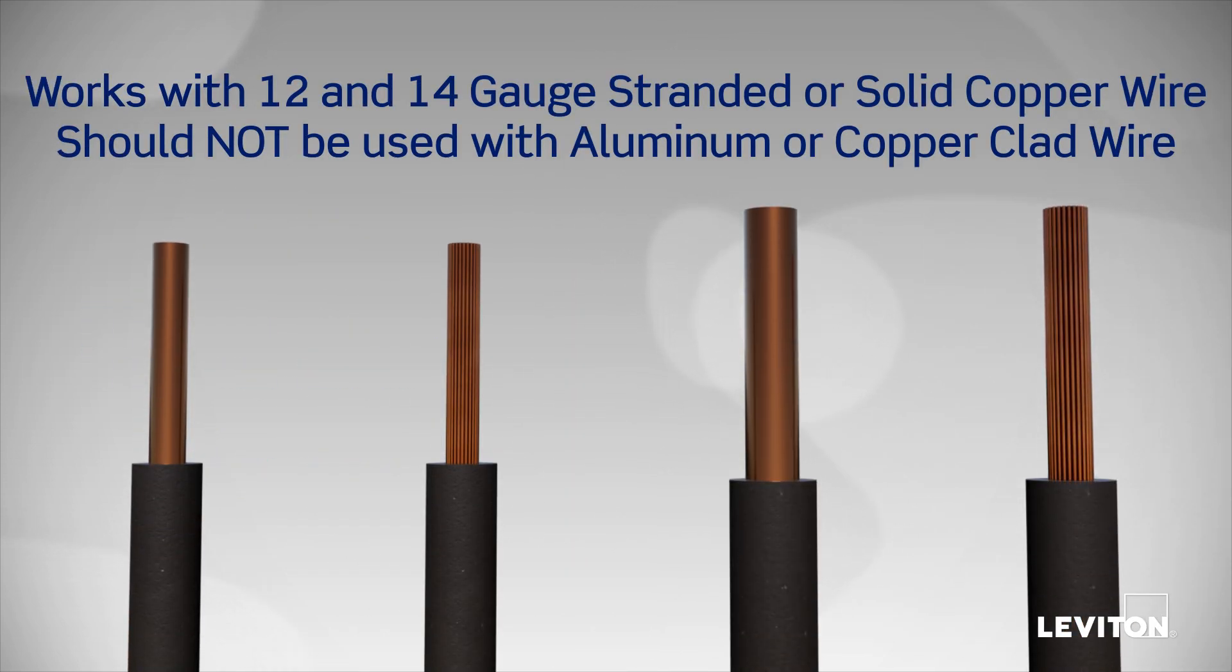LeverEdge GFCIs work with number 12 and 14 gauge stranded or solid copper wire and should not be used with aluminum or copper clad wire.